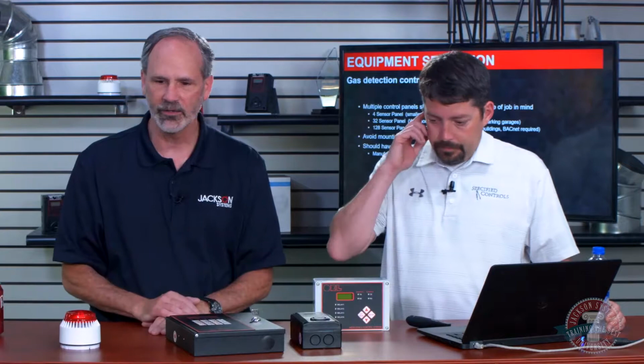Most of the time, we don't suggest sending all that data up there. We put out two alarm contacts: one that says you have a failure on your system, and one that says you've been above 50 parts per million for 10 minutes or whatever, notifying you there's not a failure, but you do have a high level. A high level and a failure contact into a building automation system is a much more economical way to do it. If you do decide you need to get all those points in there, we can help with that.